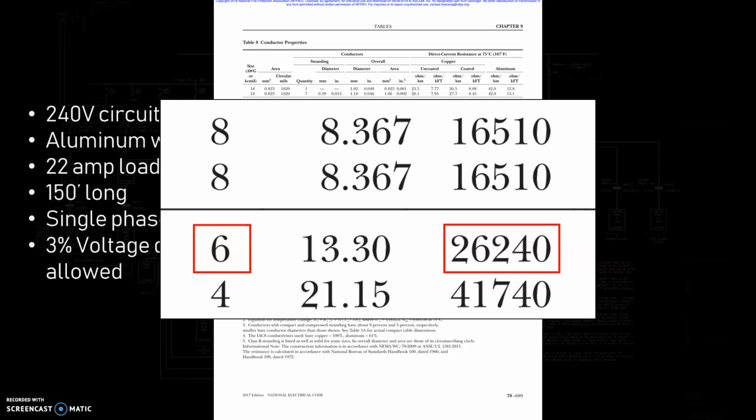That's probably the most common version of this formula. It's definitely the most helpful, most productive. But you will see a decent mix of either formula, so try to get used to using either. Biggest thing is knowing you check Chapter 9, Table 8. You can go from CMA to AWG wire size and vice versa. Okay, so there's your voltage drop lesson.